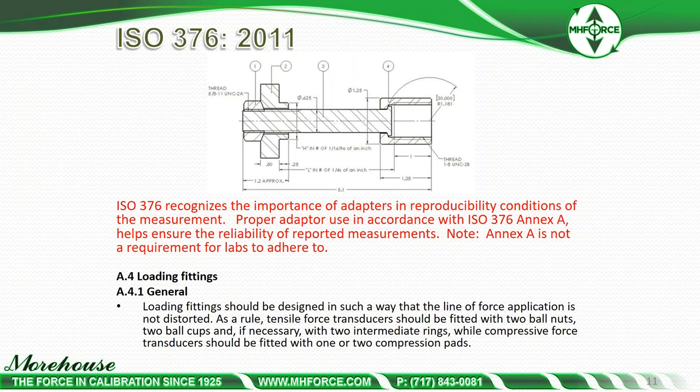ISO 376 section A.4.1 says loading fittings should be designed so that the line of force application is not distorted. As a rule, tensile force transducers should be fitted with two ball nuts, two ball cups, and if necessary two intermediate rings, while compressive force transducers should be fitted with one or two compression pads.